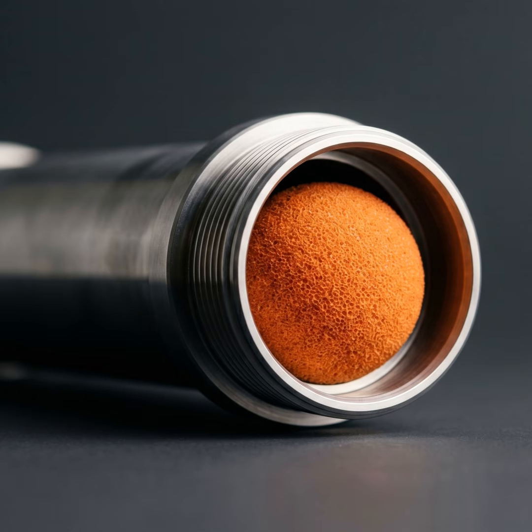That brings us to the critical operational detail, the closed-loop design. Okay. This isn't a manual process where someone dumps a bucket of balls into a tank. It is an automated, completely closed-loop cycle. There is a highly specialized catching mechanism called a ball trap. A ball trap. Yeah, and it's installed directly at the discharge end of the condenser. Okay, walk me through that cycle. So, the balls are injected into the water flow at the inlet of the chiller. They squeeze through the hundreds of condenser tubes doing their physical cleaning work. Wiping away the scale. Exactly. The moment they exit the tubes at the other end, they immediately hit this mechanical trap.